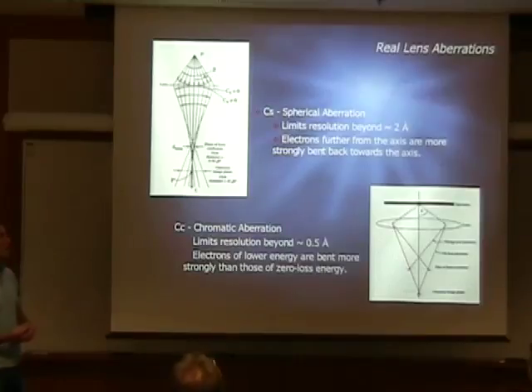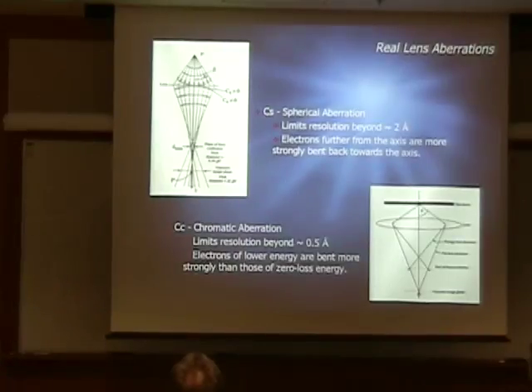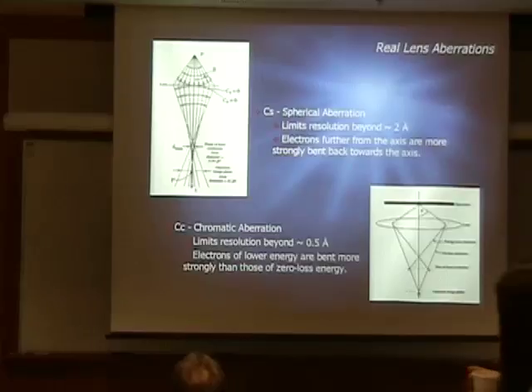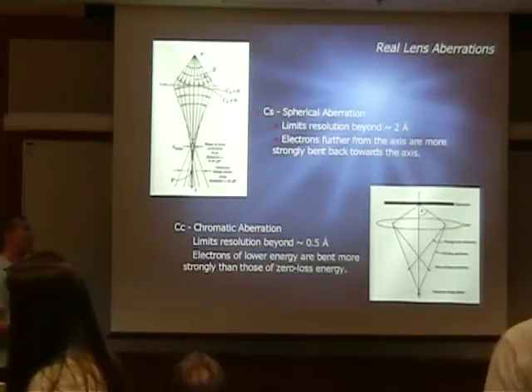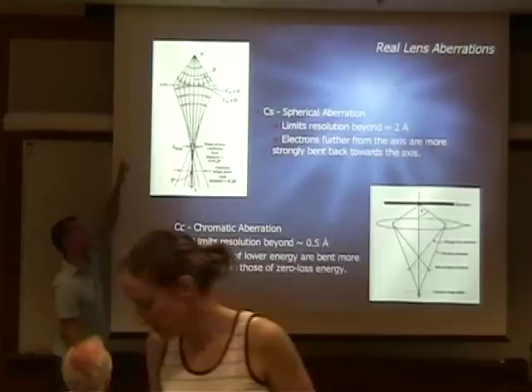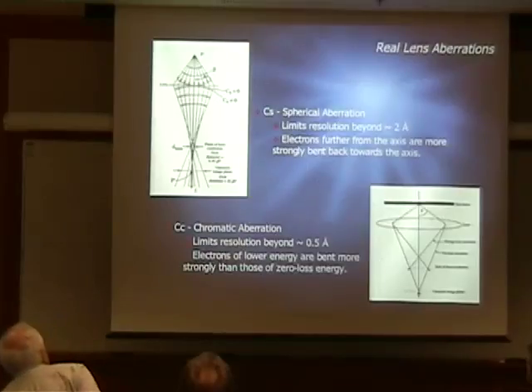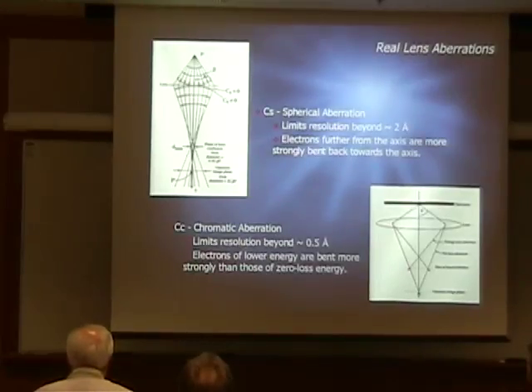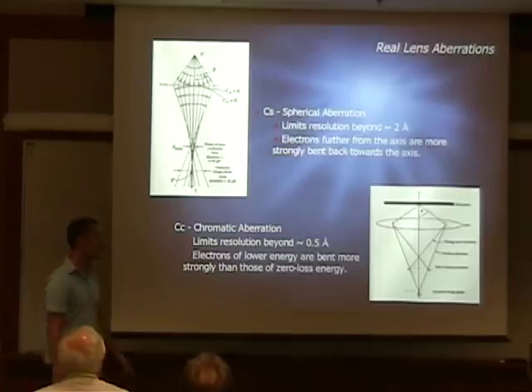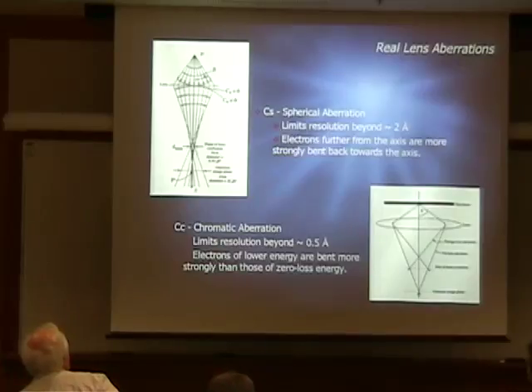In the microscope we have real lens aberrations. CS, the spherical aberration, is the aberration in the lens caused when electrons that are further from the axis are bent even more strongly towards the axis, so they never arrive at the same spot. If you're imaging a point, you actually wind up imaging a disc. Because of that, you have an inherent size limitation. The same type of thing is involved with chromatic aberration, but only with electrons of different energies, where the lower energy electrons — those that show some loss — are bent more strongly as well.